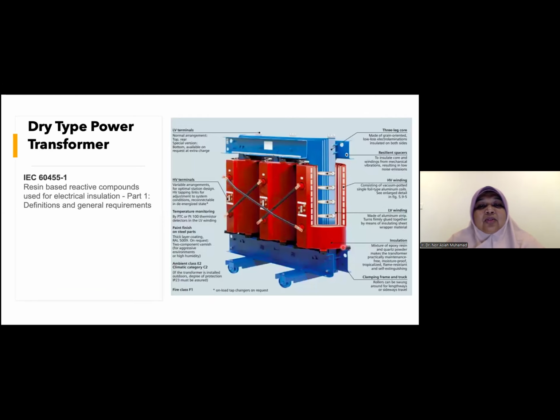Okay, so we go to the next type of power transformer, which is the dry type. The basic construction of the transformer is the same. We have the core, we have the winding, high voltage winding and low voltage winding. But instead of being immersed in oil or gas, this transformer is covered by a solid material, most of which is epoxy.